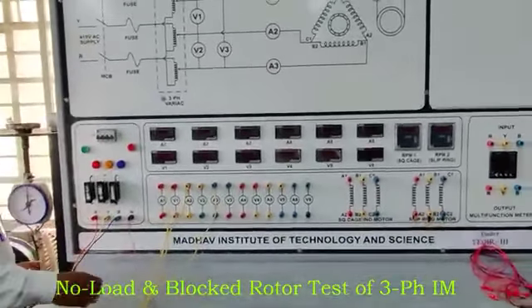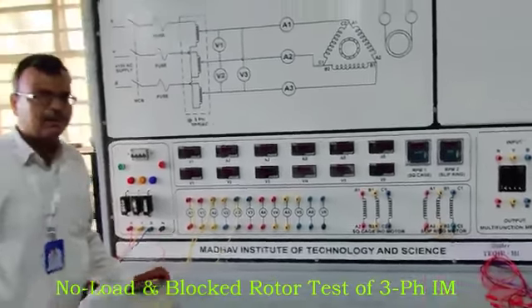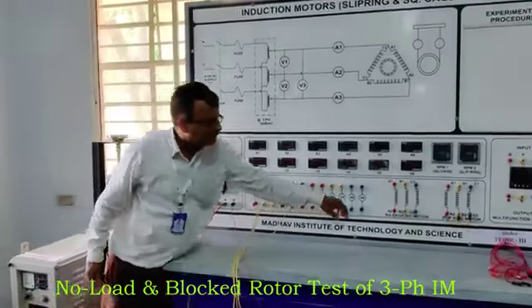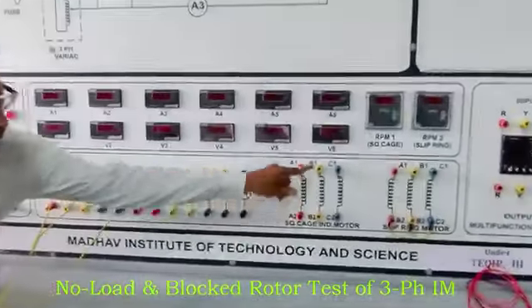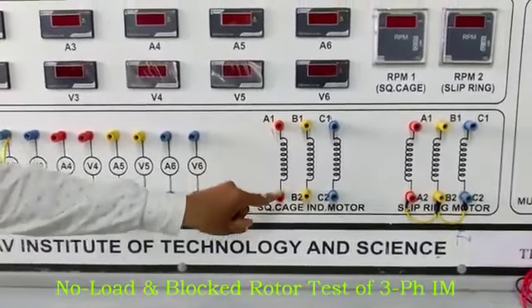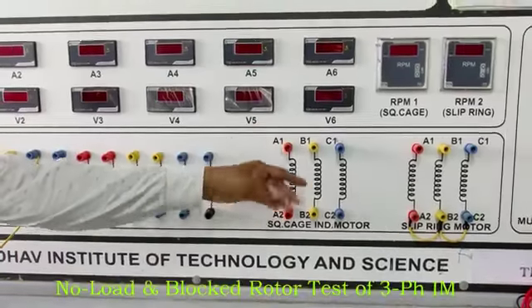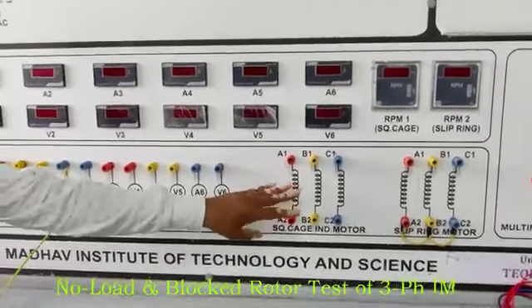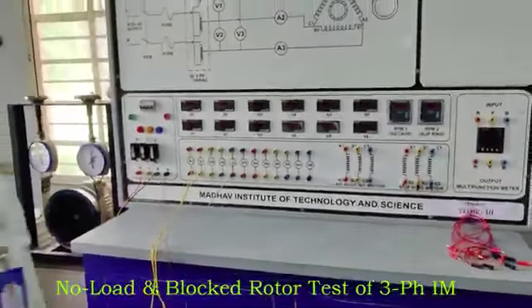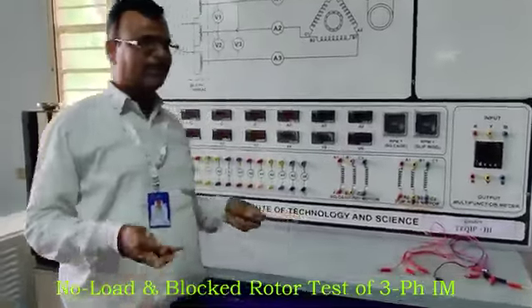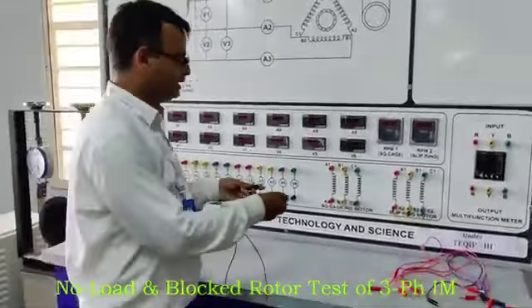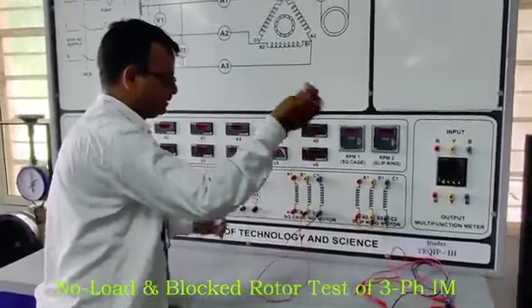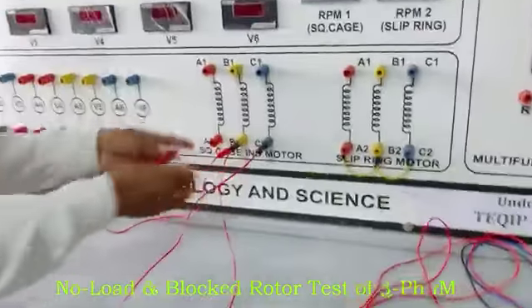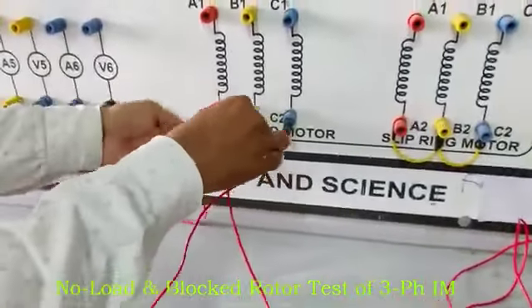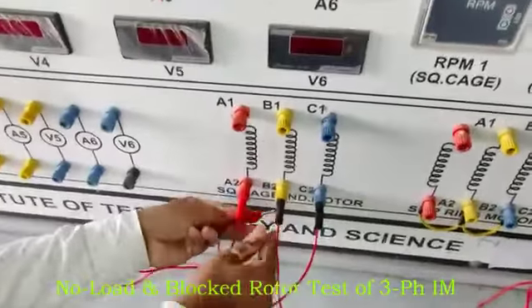We will connect the star connection. You can also connect delta, but we will connect the star connection. How to connect the star connection? You know, in a star, similar points are connected, either the starting or the finishing ends. So see that these are the 6 terminals, A1, A2, B1, B2, C1, C2. Depending upon the connections, you may connect in star or delta. So we are considering only star fashion. Clear? And how to connect in star? In star fashion, you have to create a neutral point, a star point. These are common points or neutral points. These terminals connect here and this one here, so it is the neutral point.